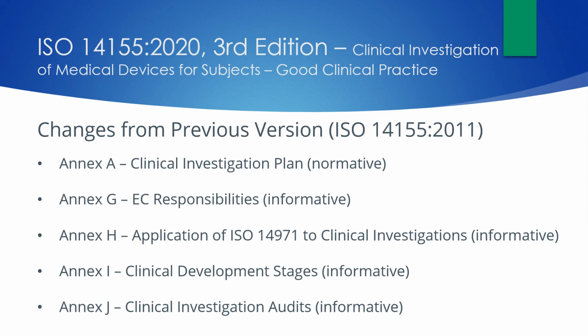Several annexes have also been updated or changed from the previous version of the ISO 14155 standard. Annex A, which is Clinical Investigation Plan, is a normative annex and includes guidance of statistical considerations. Annex G, EC, so Ethics Committee Responsibilities, is an informative annex, and it has an inclusion of guidance for ethics committees. Annex H, this is the application of that ISO 14971 standard to clinical investigations. It is also an informative annex, and it reinforces the thought of risk management through the process of the clinical investigation. So planning to results. So when you first start out planning your study, to the CIP, to the monitoring, all the way to your report.